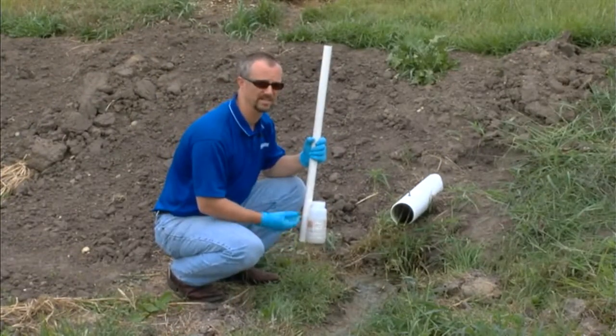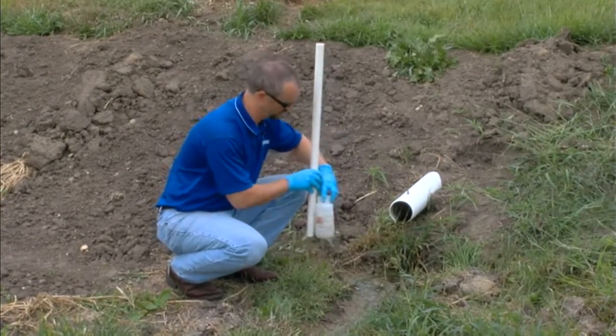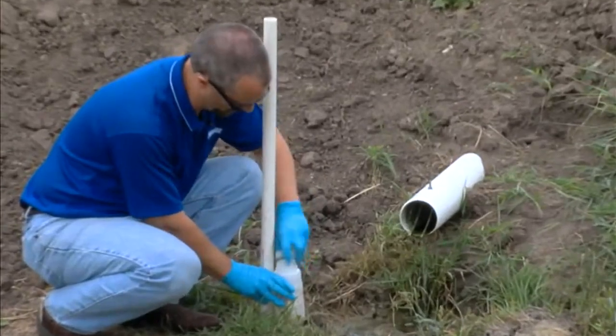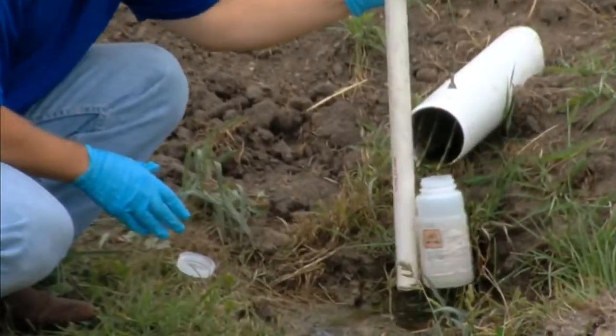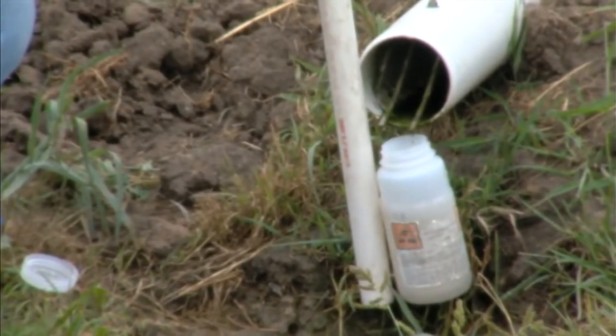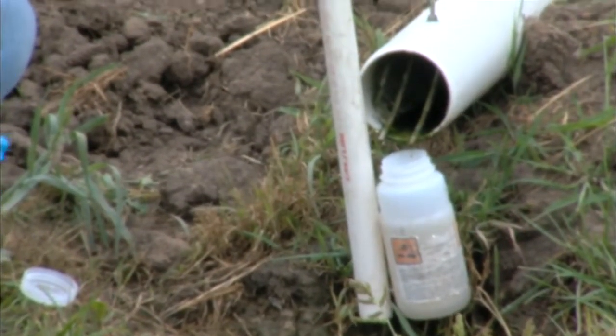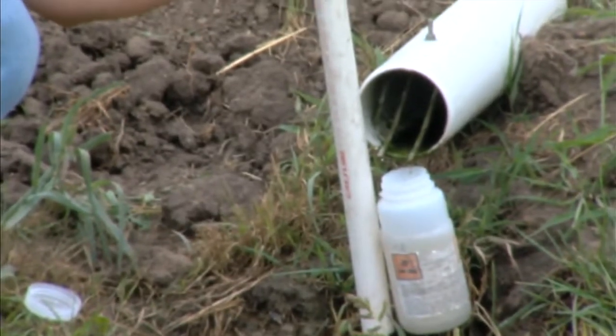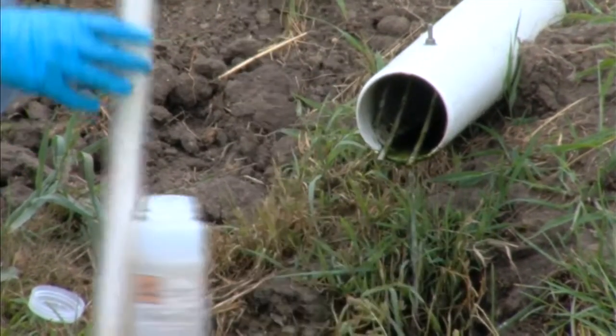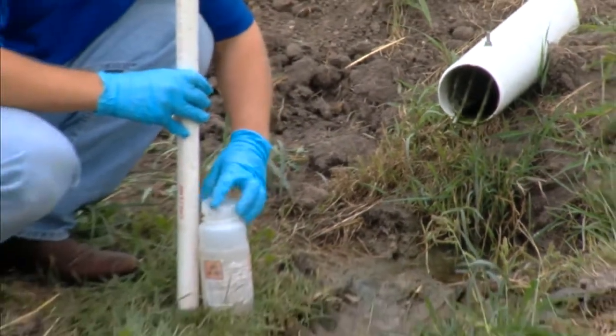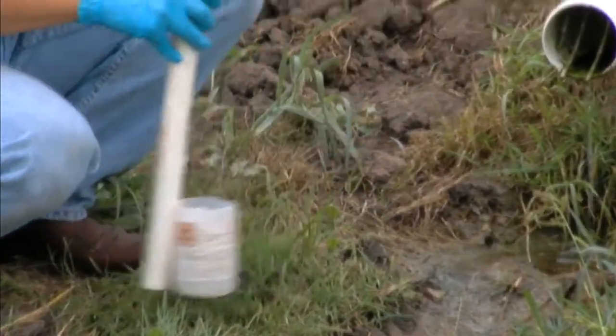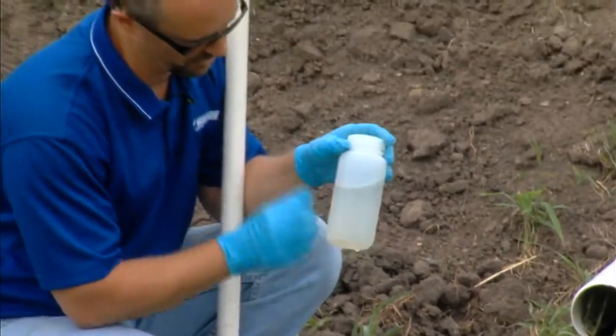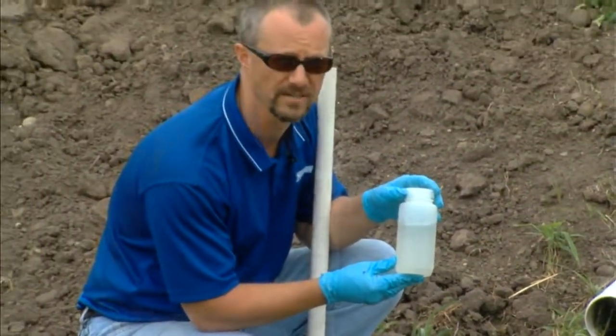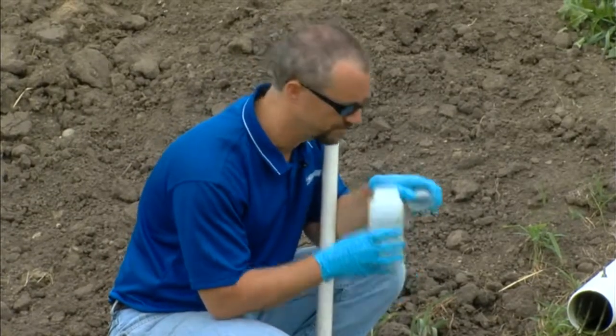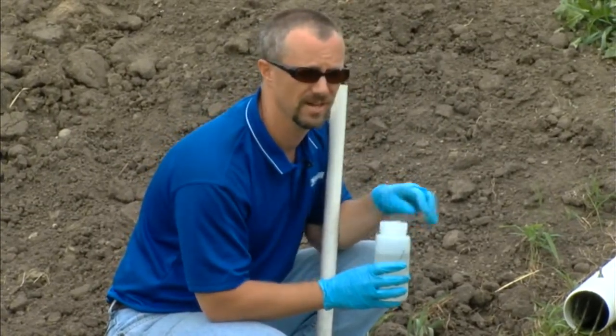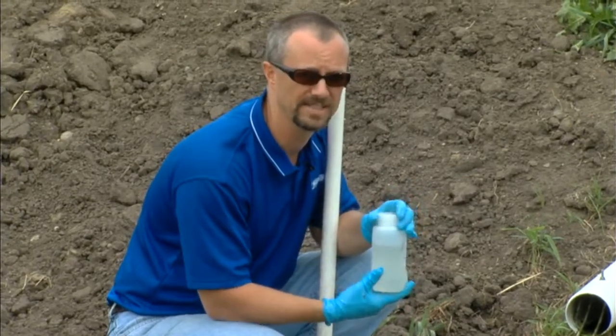Last but not least, we're going to want to take a sample of the effluent coming out of the system. We have our sample bottle in our collector. In this case, we've got an open discharge pipe, so it's very easy to collect our sample. You may have a pump tank or a D-box that you're taking that sample out of for a subsurface discharge, but you've collected a decent amount of sample there. You can take a look at it now. Make sure it's relatively clear, like a glass of water. Make sure you don't have any floating particles, large solid particles in there. And then also you want to smell the sample too, just to make sure it smells like just a musty, damp odor, not that septic odor.